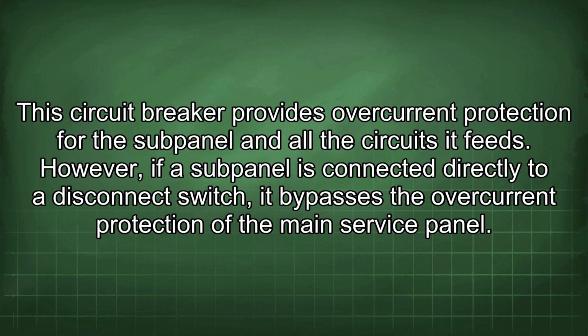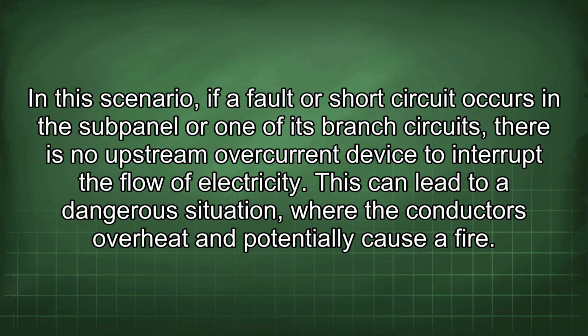However, if a subpanel is connected directly to a disconnect switch, it bypasses the overcurrent protection of the main service panel. In this scenario, if a fault or short circuit occurs in the subpanel or one of its branch circuits, there is no upstream overcurrent device to interrupt the flow of electricity. This can lead to a dangerous situation where the conductors overheat and potentially cause a fire.